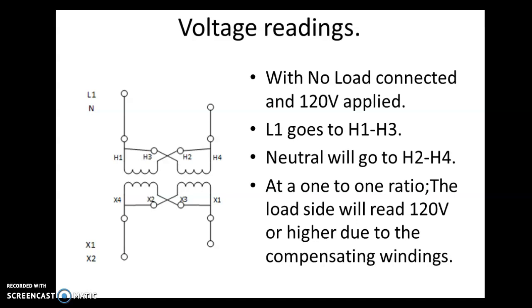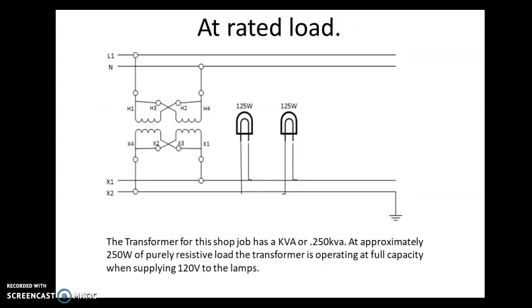At a 1-to-1 ratio, the load side will read 120 or higher due to the compensating windings. So we will read that out of the X2, X4 connection and the X1, X3 connection with our digital multimeter. On the secondary side of a transformer, when you have a single phase transformer, it's also often referred to as X1 and X2. This right now can be referred to as an isolation transformer or a control transformer as well.